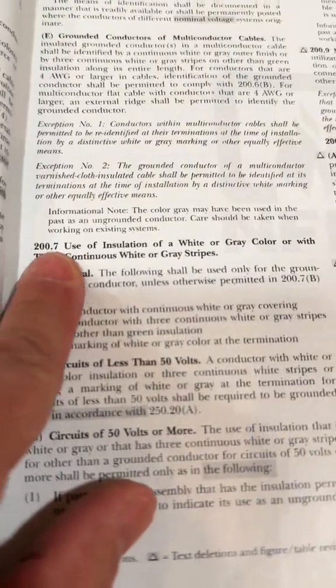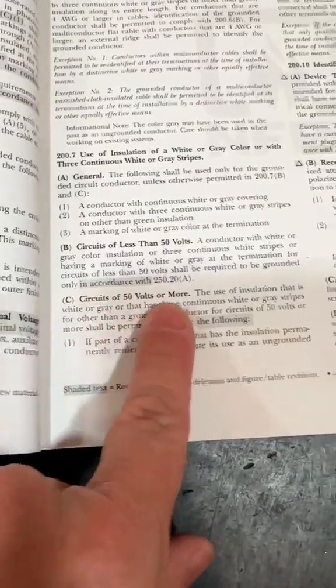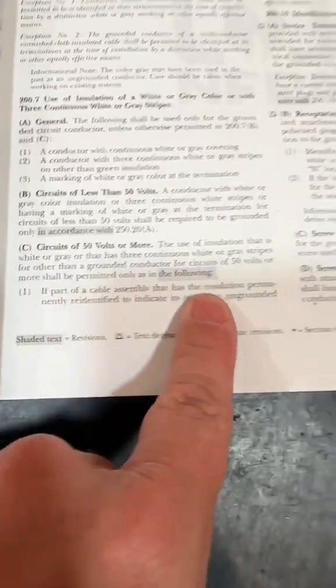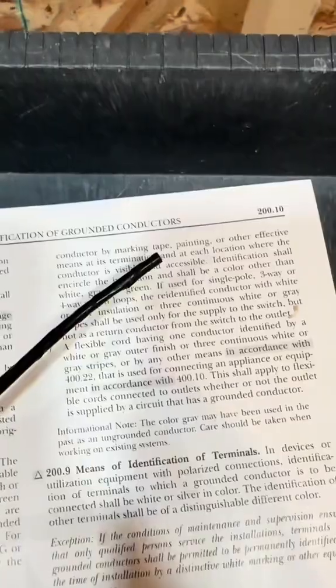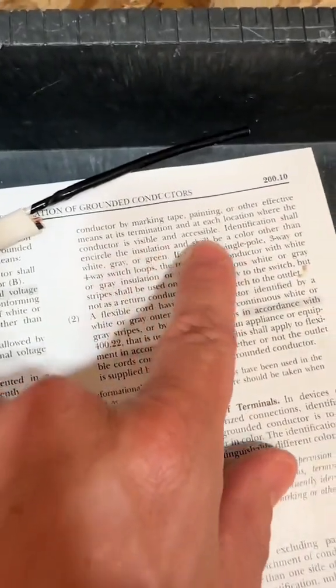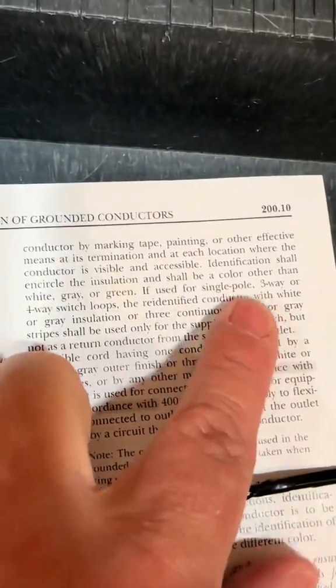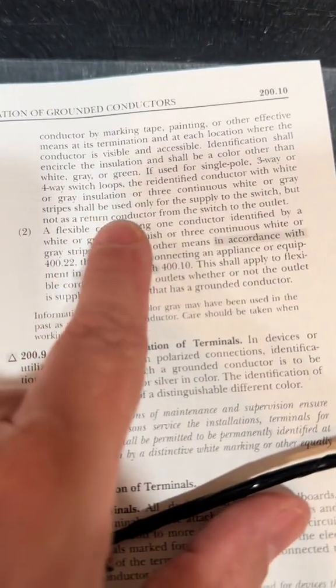Grab your 2023 electrical bible, go to page 77 — 200.7, use of insulation of white or gray color. We're in residential using 14-2, so that's a white wire. These circuits of 50 volts or more: if part of a cable assembly type NM-B, Romex is a cable assembly, the insulation is going to be re-identified by marking tape, painting, or other effective means at each location where the conductor is visible and accessible. If used for single pole, the re-identified conductor will be used only for the supply to the switch, but not as a return conductor from the switch to the outlet.